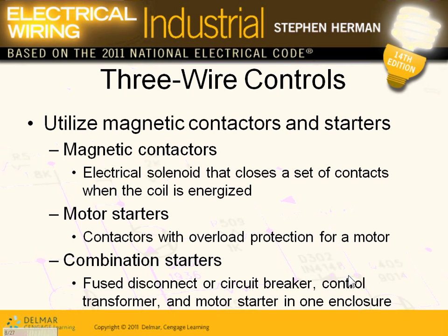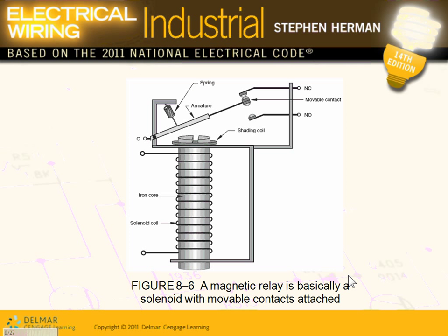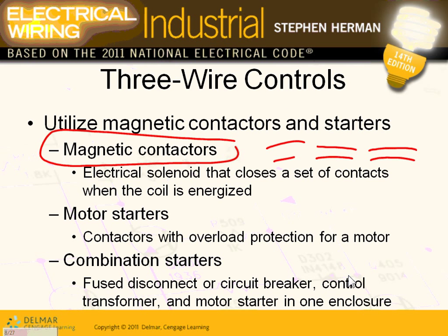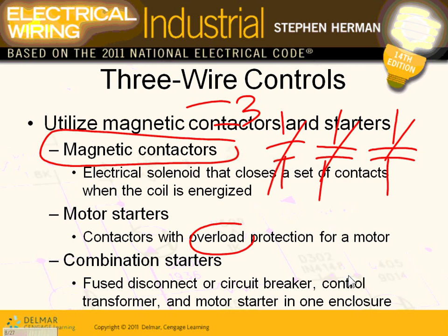Magnetic starters are the best. When you have a magnetic starter, you have to have a coil — you energize the coil and drive multiple contacts. That's the whole idea of any magnetic starter. You have a coil here; you energize the coil and it closes all contacts. You bring the magnetic contactor and add an overload to it — it becomes a motor starter.